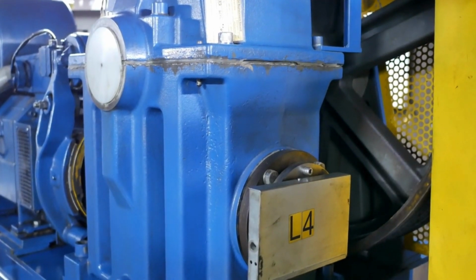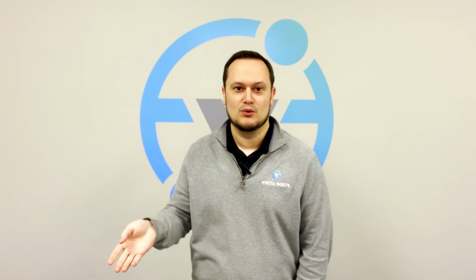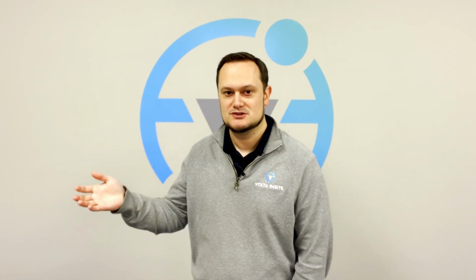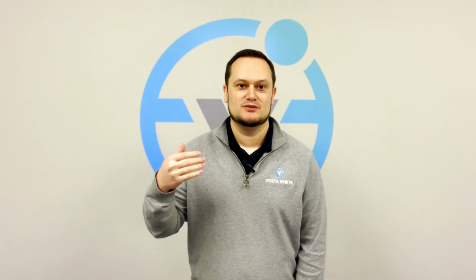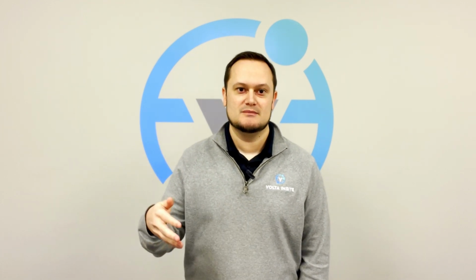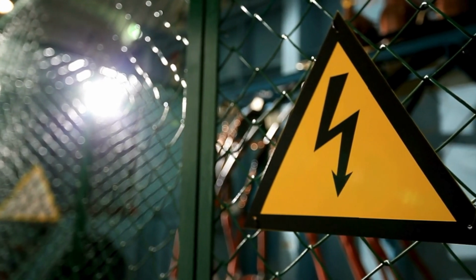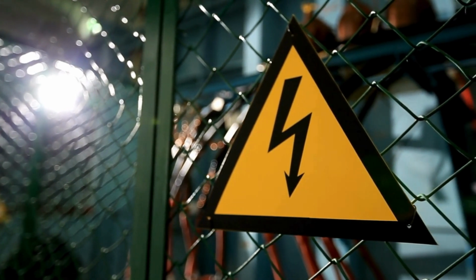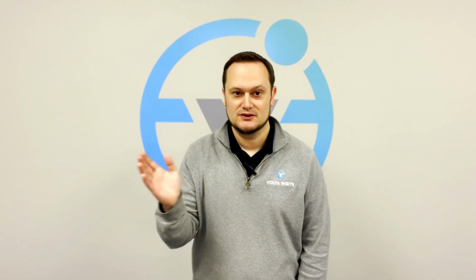So for example, if it's at a motor and you just have a couple nodes installed on your main pieces of equipment, we're going to be able to see the voltage sag or the voltage react before the current reacts. And that lets us know it's coming from upstream and it's not coming from downstream of where that node's location is. So from a motor, obviously there are things that could happen if the current does spike or if there is an overload or something jams in the load. That will create a current spike, but then the voltage will fall after. So it's a good way to just give you a clear delineation of downstream or upstream.